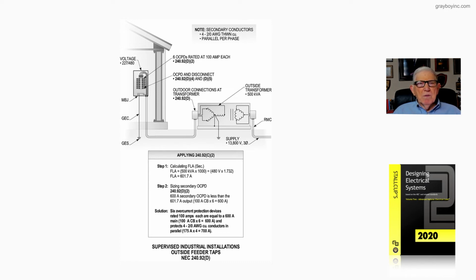Step 2, we'll apply 240.92 D as in dog 2. We have a 600 amp secondary now for the overcurrent protection. Now, if the overcurrent protection is 600 amps, where you have 6 100 amp fuses or 1 600 amp, then you have provided the protection to protect the output of the transformer.